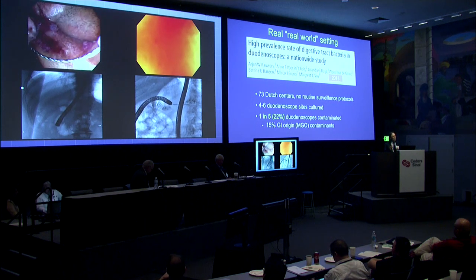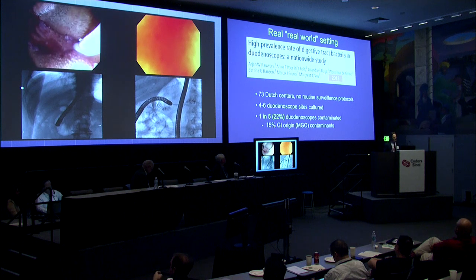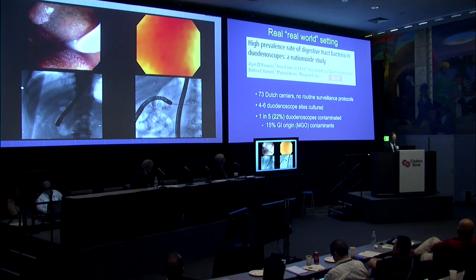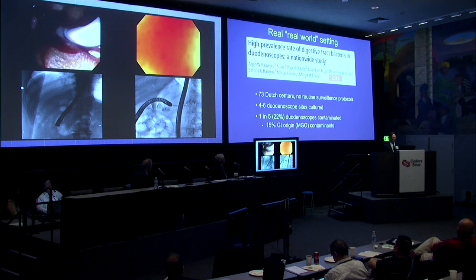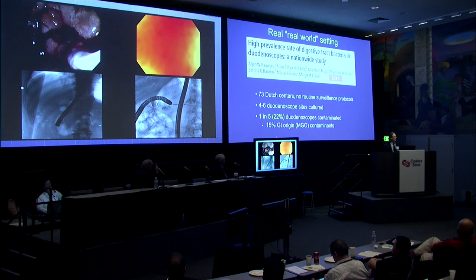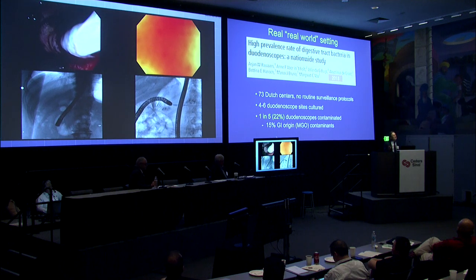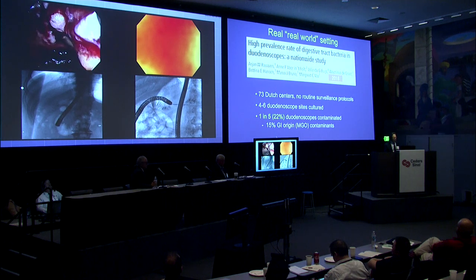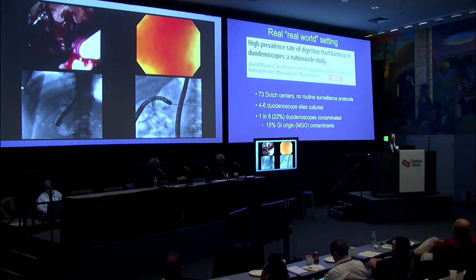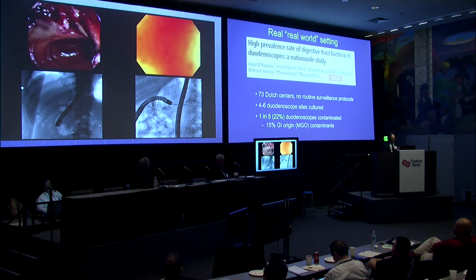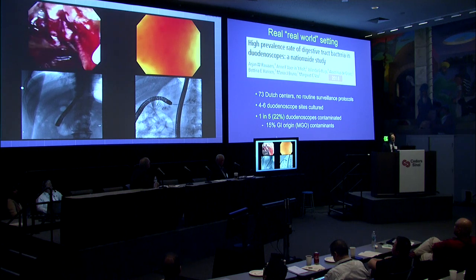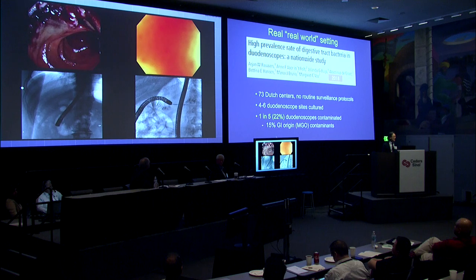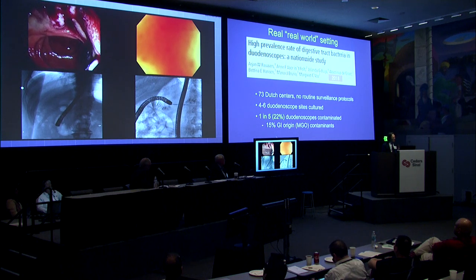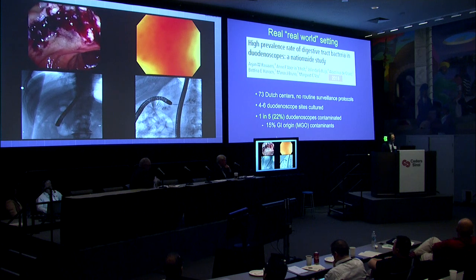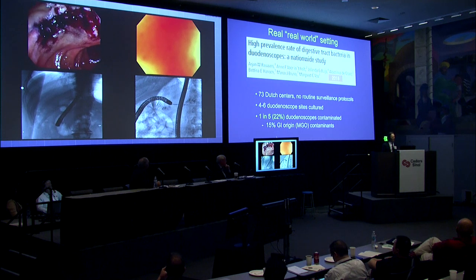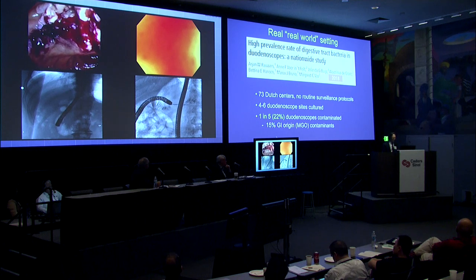But that's not even the real world setting. This is the real world setting, a study from Holland. In this study, 73 Dutch centers had no routine surveillance protocols being performed; in other words, no one was being observed, so there was no Hawthorne effect. There were 4 to 6 duodenoscope sites cultured, and it showed that more than 1 out of 5, actually 22%, of the duodenoscopes were contaminated. Of those contaminations, 15% had a GI origin. So those are potentially the superbugs we're talking about.